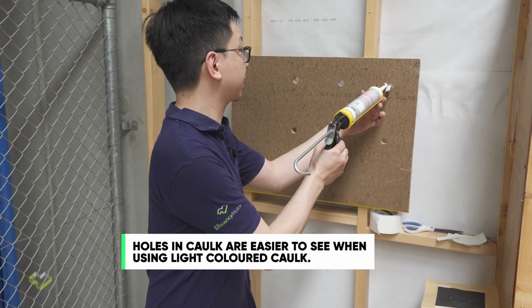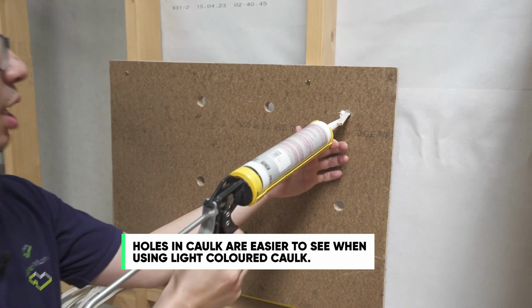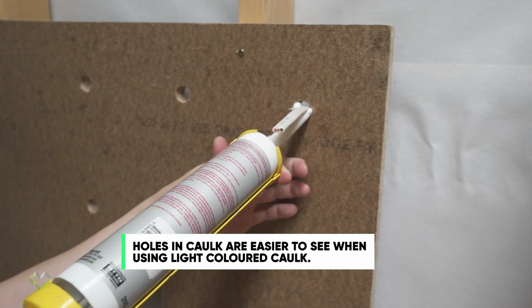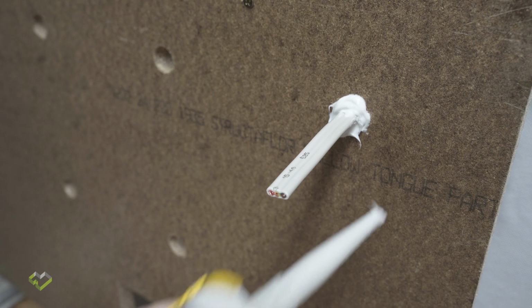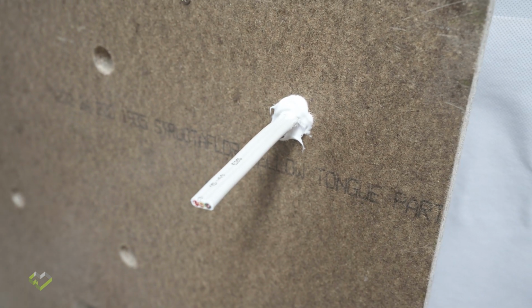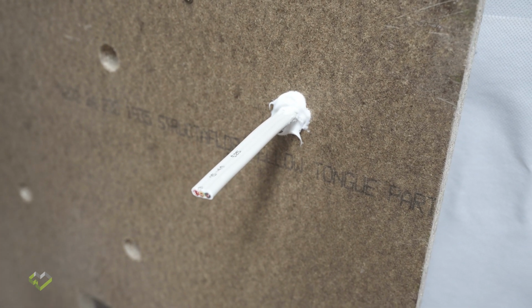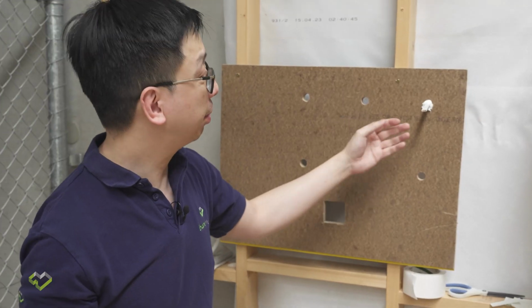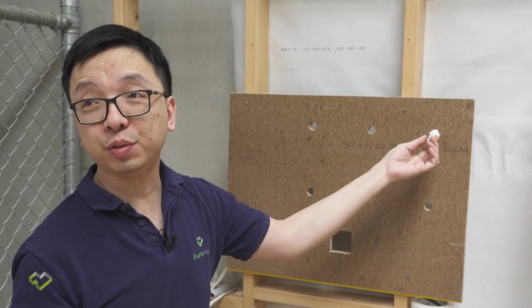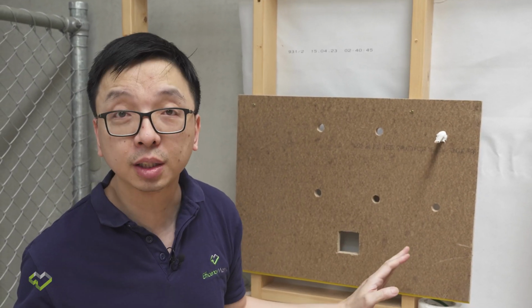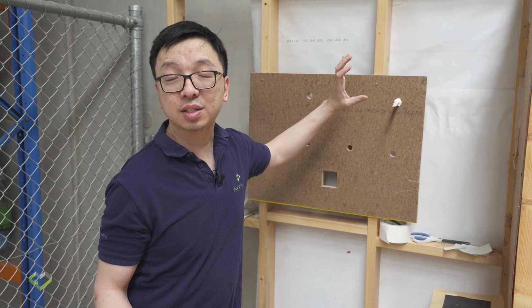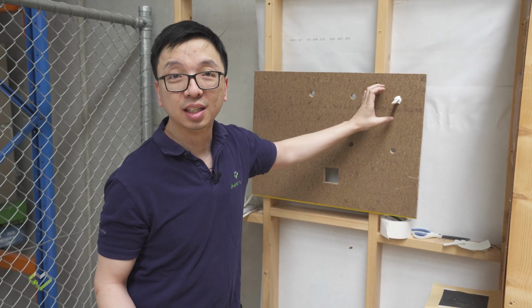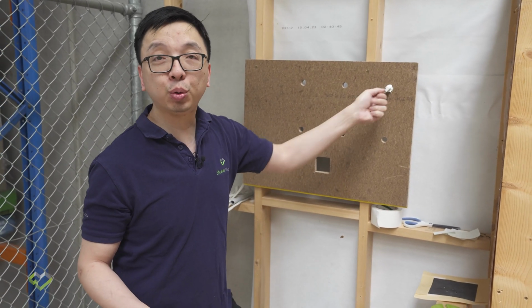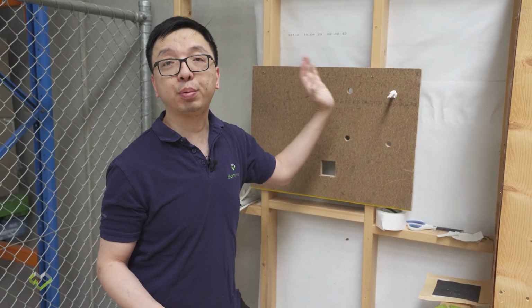It's not that hard, just squeeze the product until it fills the gap so you don't have any bubble or dead space. The process is this simple. However, this most common method has a very, very detrimental weakness. Number one, before it's dry, if anyone moves the cable, the seal is broken. Even after the sealant is dry or set, if someone starts to pull the cable, it still breaks the seal.